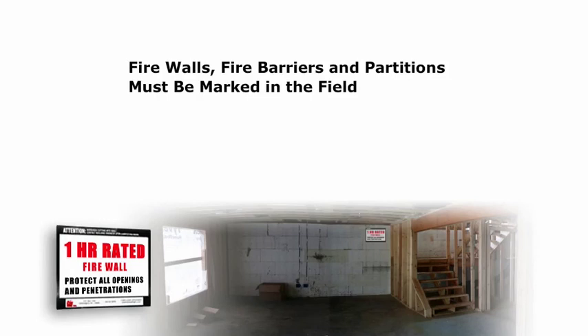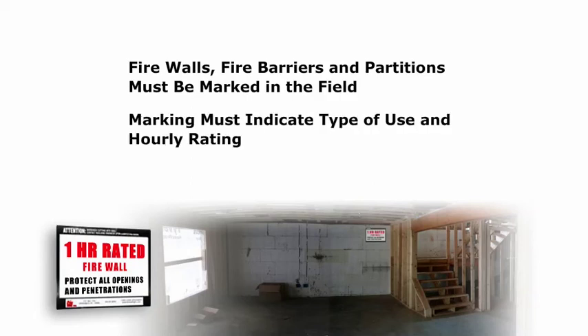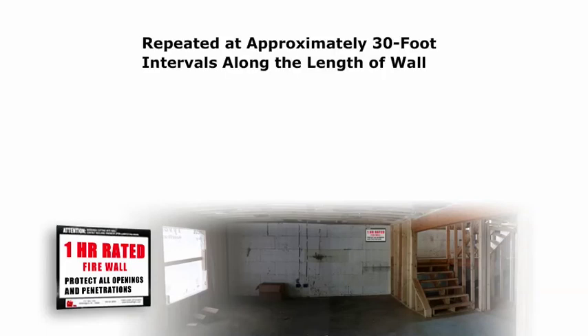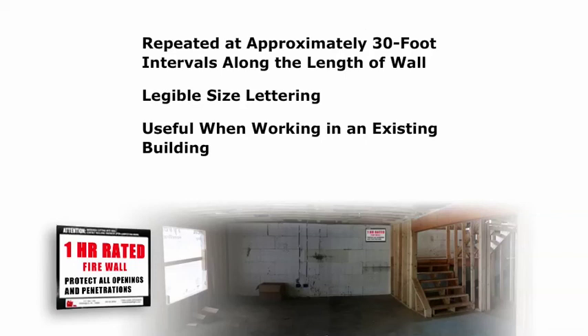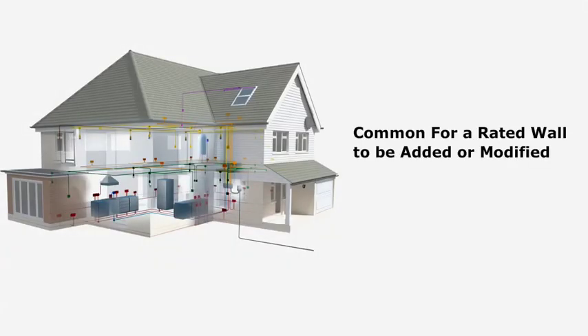The codes now require that fire walls, fire barriers, fire partitions, smoke barriers, and smoke partitions be marked in the field. The marking must indicate the type of use — for example, fire barrier or fire partition — and the hourly rating it provides. This mark can be above the finish ceiling but must be accessible. The information must be repeated at approximately 30-foot intervals along the length of the wall in legible-sized lettering. This is not required in certain residential uses with drywall ceilings, but it is very useful when working on an existing building to quickly locate rated walls.